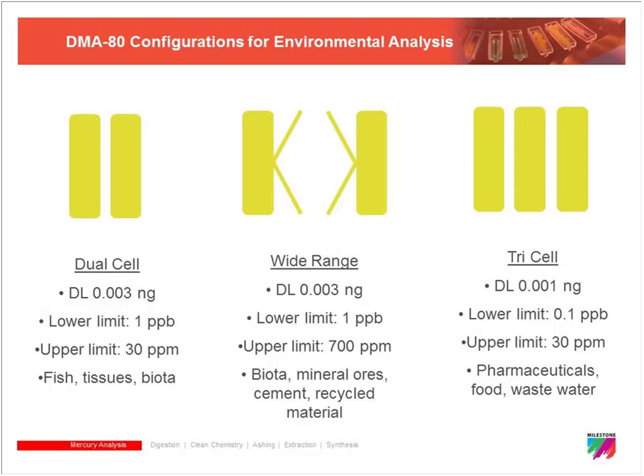We also offer a wide range system, which allows the analysis of very, very highly concentrated samples, upwards of 700 ppm. This is similar to the dual cell with the first low-range cell, but we add a much higher range cell onto the end of the system to be able to handle such a high concentration of mercury. This is most commonly used in the mining industry, where they can be coming in contact with such high concentration mercury samples. Again, the most common configuration for tissue and biological samples would be the dual cell configuration.